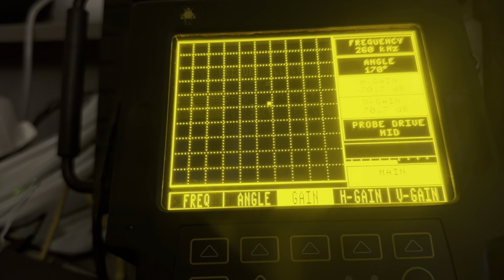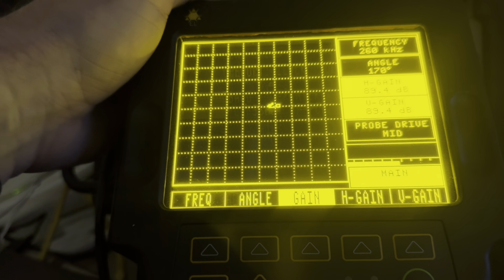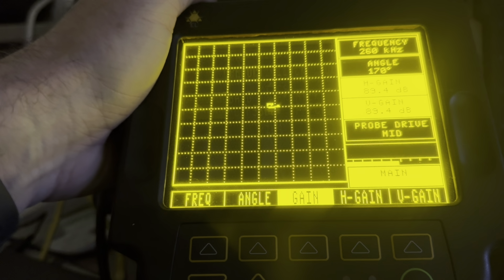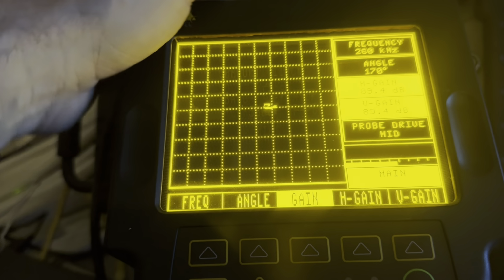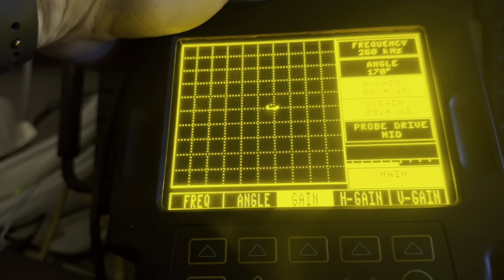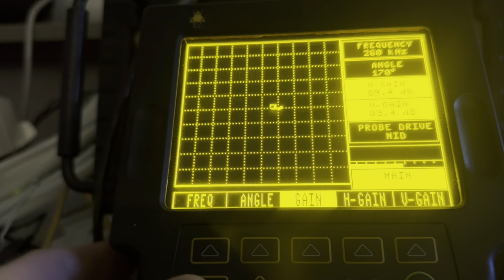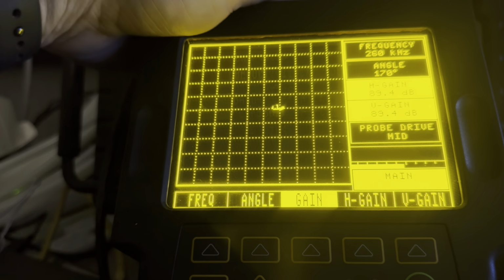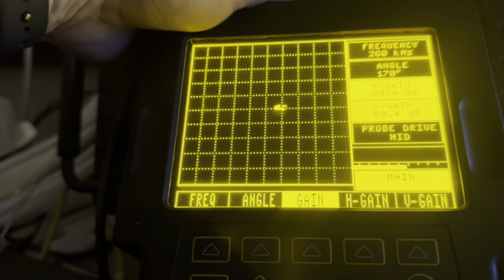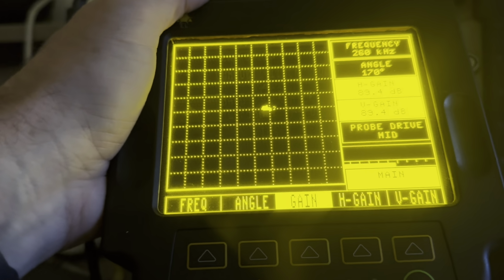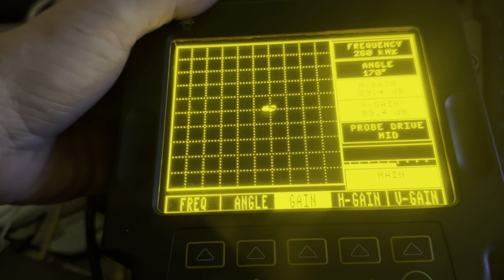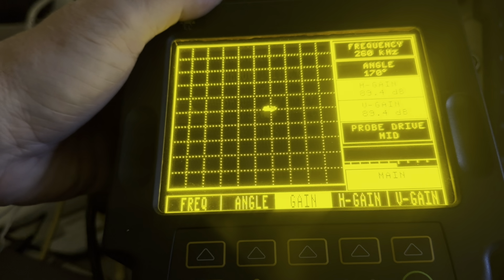And then we'll try to crank up our gain, see if that does anything. Okay, it's not doing much, but I still have a couple other selector settings on here. Now, if I didn't know any better, I would probably switch over to reflection mode, which I just turned the selector at the top. That doesn't do anything, so that's probably not the issue. Then I'll go over, and remember I have that other switch. It says low, off, and high, I think.